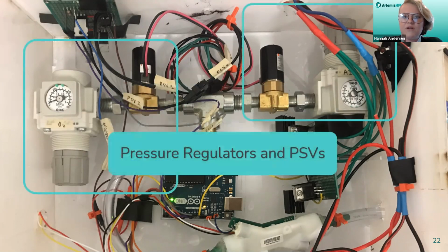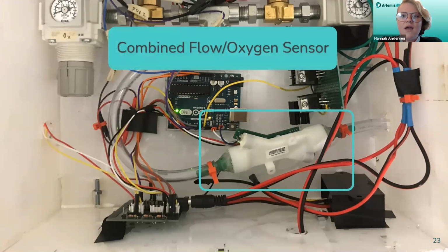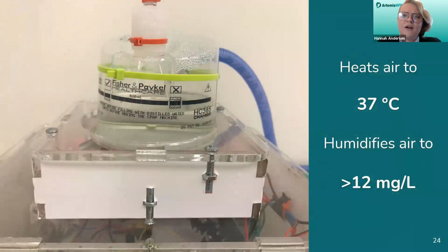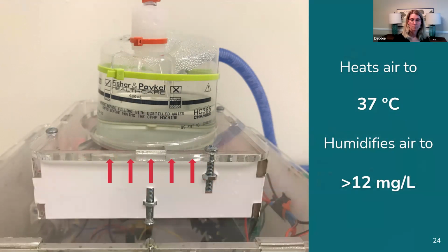And this versatility has been achieved using a pair of pressure regulators and proportional solenoid valves that are controlled by a combined flow and oxygen sensor and a robust control algorithm in our blending system. The blended air from this system then travels to a humidification chamber, which sits atop a heater. And this metal heater transfers heat to the humidification chamber, which is full of water. And thus the air is heated to 37 degrees Celsius and humidified to 12 milligrams per liter or more. And this warm, high-flowing air exits the chamber before traveling to John through a nasal cannula.